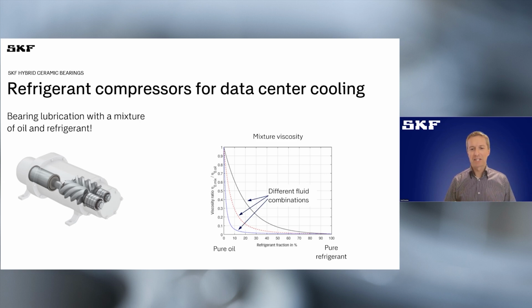One of the applications that really showed us those extreme benefits that hybrid bearings offer is the application of pure refrigerant lubrication, abbreviated PRL, where we are actually capable of lubricating a rolling element bearing using ceramic rolling elements with a pure refrigerant. That is all the way on the right-hand side of that graph, while still maintaining a high level of robustness.